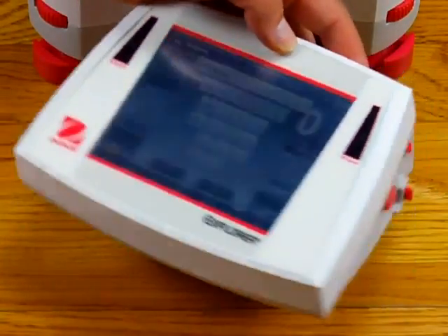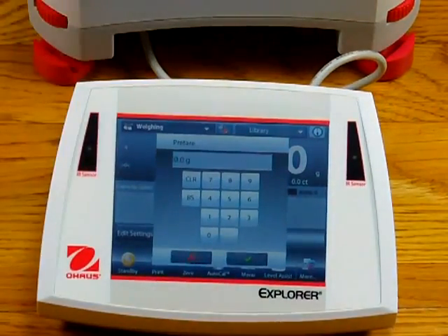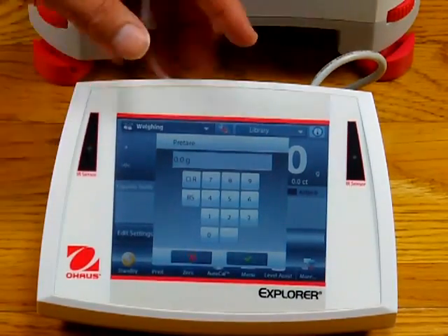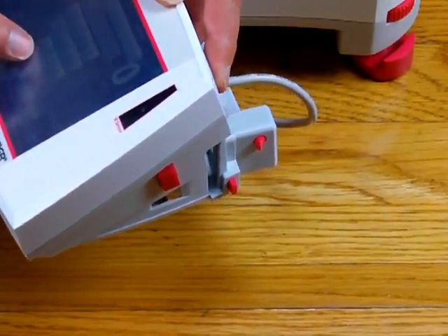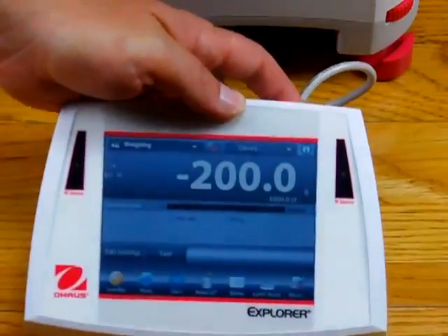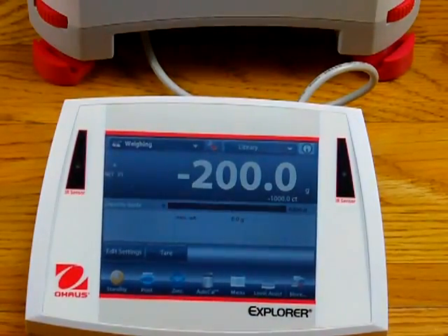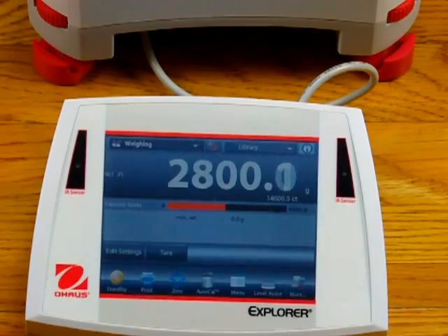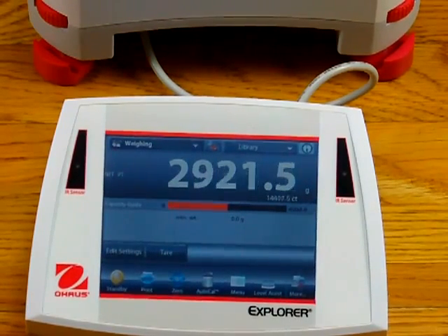This feature here is pre-tare, so we can pre-tare a value. If we had, for example, a weigh dish that always weighed 200 grams, we can enter a weight of 200 grams, hit OK, and now it's automatically set to minus 200 grams. So if I put on a 3 kilogram weight, it will now show 2,800 because of the pre-tare. Real nice feature with the Ohaus balance.